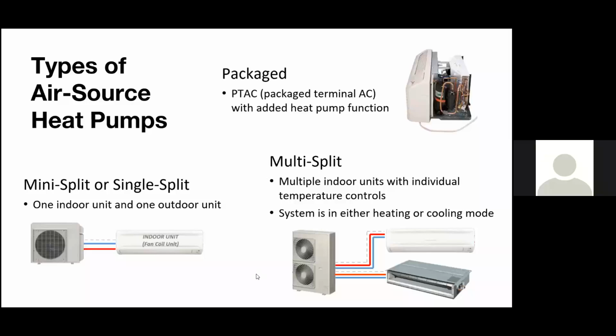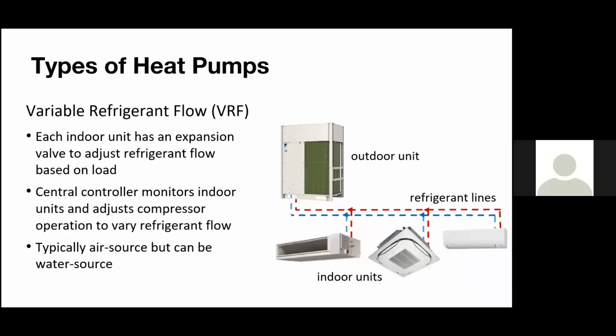So moving on to VRF, or variable refrigerant flow. This is the big brother version of the splits. VRF, it's extracting or ejecting heat from the outdoor air source machine. We also have water source machines as well. So these machines are a little bit larger than your usual mini splits. They can be modular, where you can tie multiple of them together into one refrigerant circuit, increasing the capacity of the system. The compressor lives in that outdoor unit, all inverter, variable speed compressors, very efficient machines. And then each indoor unit has its own expansion device and its own thermostat. And each indoor unit will modulate the amount of refrigerant depending on what each needs. So you vary the amount of refrigerant based on demand, hence the term variable refrigerant flow.